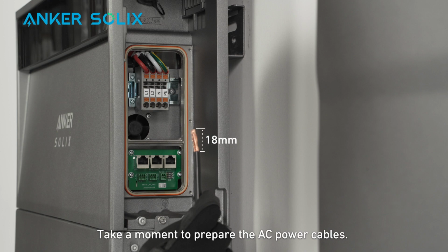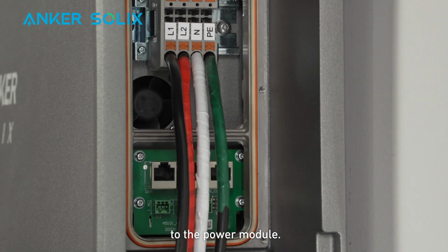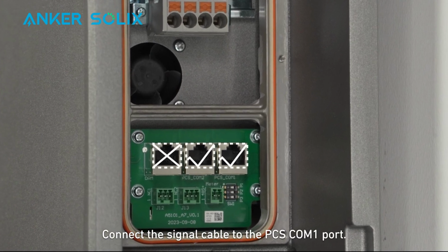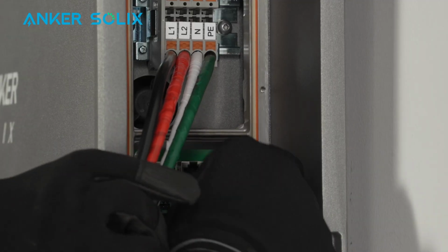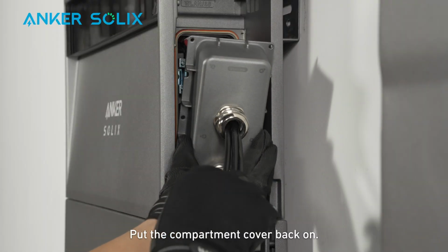Take a moment to prepare the AC power cables. Strip 18 millimeters of insulation. Connect the ground, neutral, L1 and L2 cables to the power module. Connect the signal cable to the PCS COM1 port. Put the compartment cover back on.